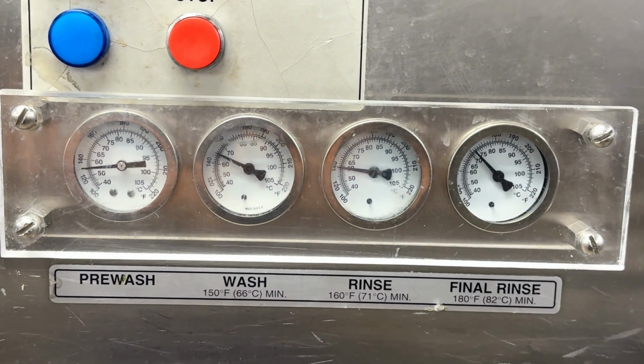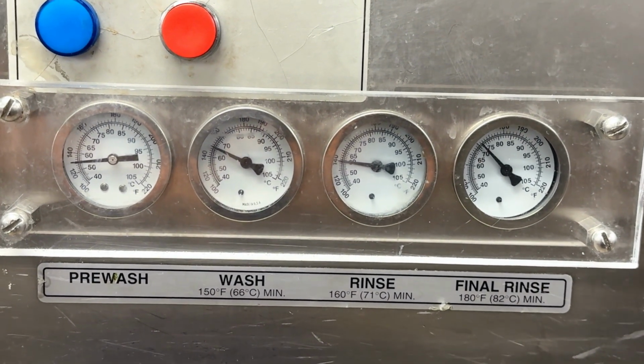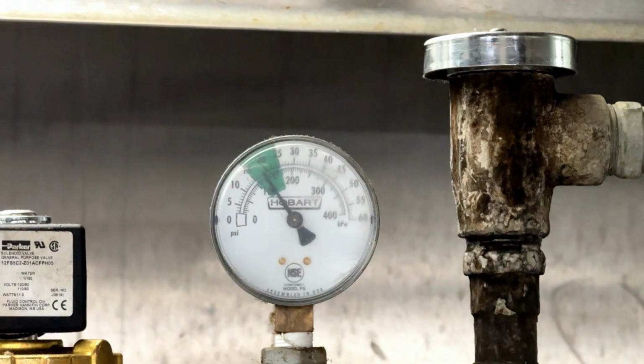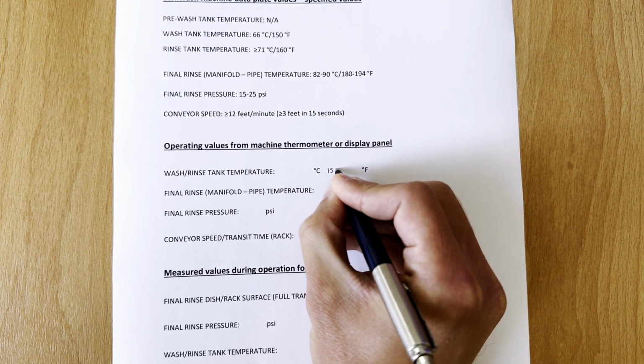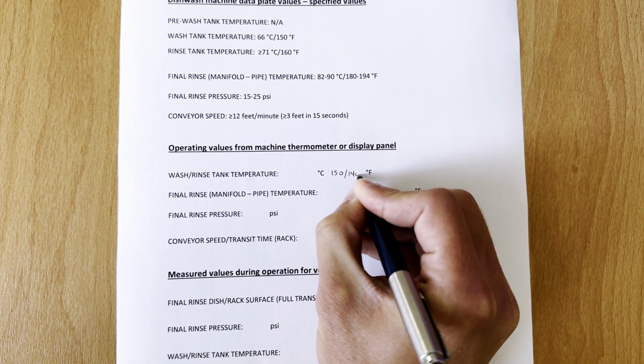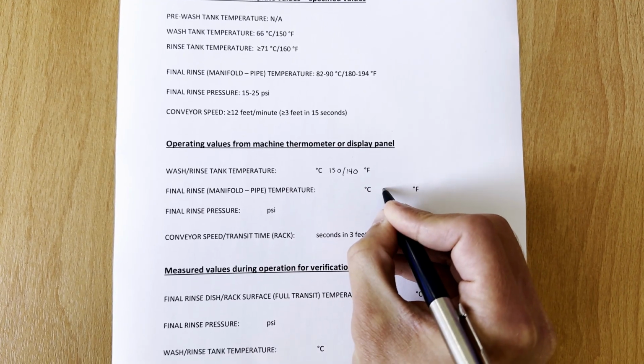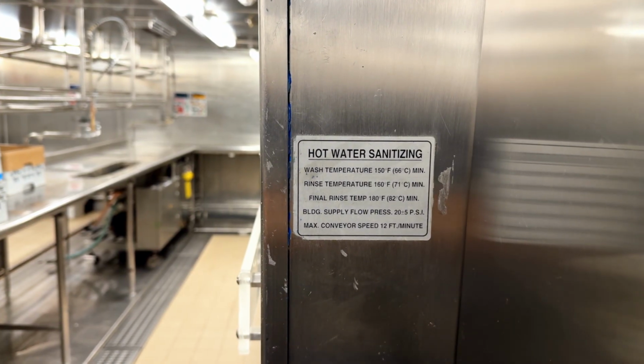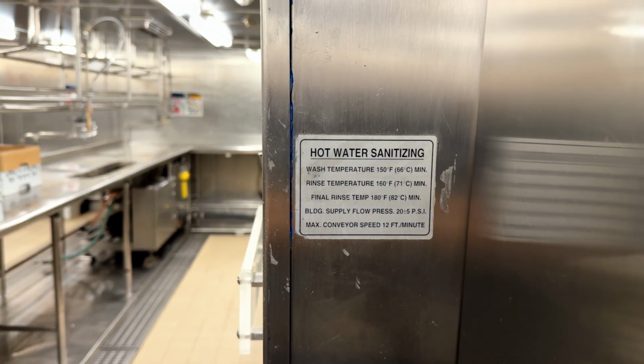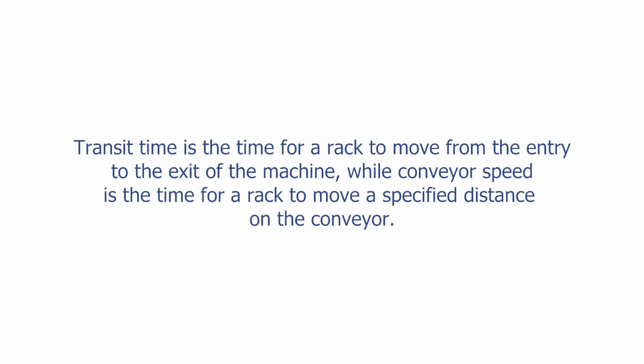Observe the mounted thermometers on the machine exterior, and write down the values displayed for pre-wash tank, wash tank, rinse tank, pressure of final rinse, and manifold temperature of final rinse. Compare each value to the earlier recorded values specified on the machine data plate. Transit time is the time for a rack to move from the entry to the exit of the machine, while conveyor speed is the time for a rack to move a specified distance on the conveyor.